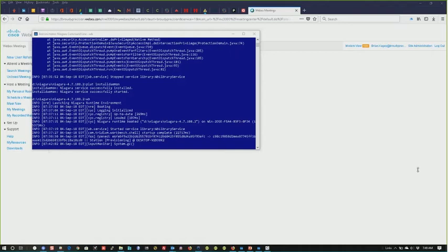I've got a question about provisioning. Is there any kind of mechanism in there for a corrupted file? Like, I had a site where I did a manual backup, and as it was backing up, I noticed that it completed extremely quickly. It looked like everything completed. Well, when I did a station copy, the station copy actually failed because there was a corrupted file. Is there anything in the backup of the provisioning that would see that? What constitutes it failing versus completing okay?